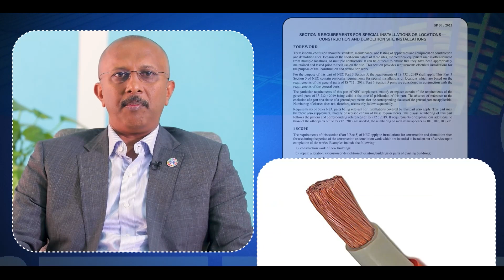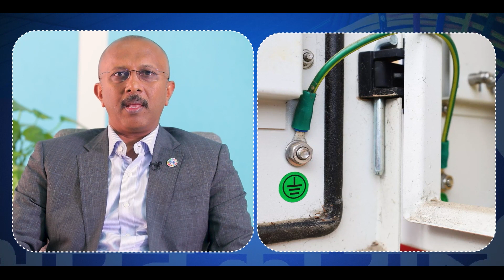These are locations where the safety measures used in the general part of the installation cannot be applied. For example, as a measure against electric shock from a fault, the recommended safety measure called protective equipotential bonding and automatic disconnection of supply may not be applicable. Sometimes other measures such as double insulation and supplementary bonding are mandatory in some of these locations. These are detailed in the respective sections of Part 3, hence Part 3 needs to be read in connection with Part 1.